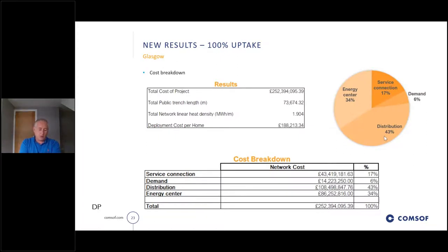One thing that's really important to say is what we're observing in the gaps. There is no actual gas cost data or heat load data in this - it's all from GIS data. The early observation is: who has got all the gas billing data for the buildings in this area, and why can't that be made publicly available for these sorts of projects? What's under the ground was also major feedback from Vital Energy's work, particularly around Strathclyde University, where even ground-penetrating radar wasn't really showing whether services were alive or dead. What's down there? How deep do you have to go? So aspirationally brilliant, but be ready to be thinking in terms of £250 million for this sort of area.